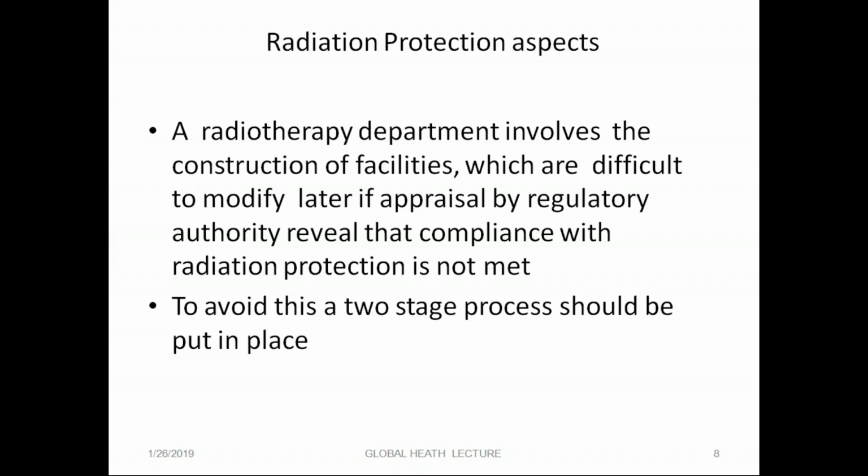One, if you're going to set up a radiotherapy facility, you would provide information and a description of the facility and the equipment that you're going to use to the National Radiation Authority, about the managerial organization, arrangements, training, and the personnel that will be operating the procedures, so that they are aware of what kind of radiotherapy program you are planning to have, and if they have any advice, they give it ahead of time.